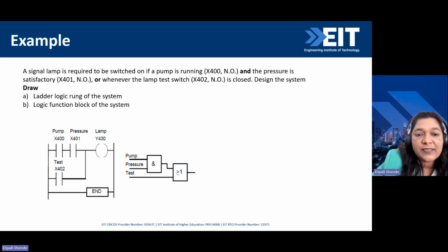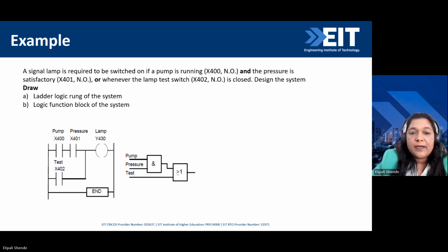Whenever the lamp test switch is closed, that means this switch is closed, design the system and draw a ladder logic and logic FBD for this. Now the condition is both should satisfy: pump is running and pressure is satisfactory. In that case, just switch on the lamp. Or when X402, the lamp test switch, is closed, it should be on. So we will write like this.